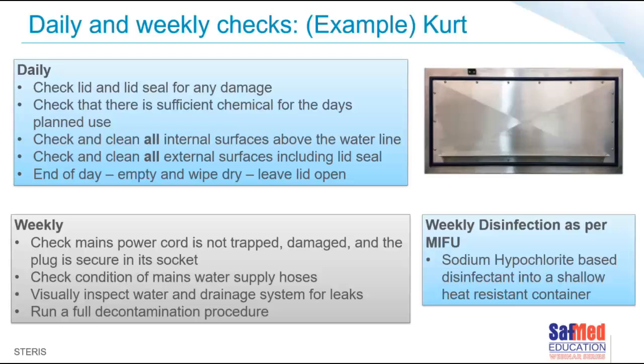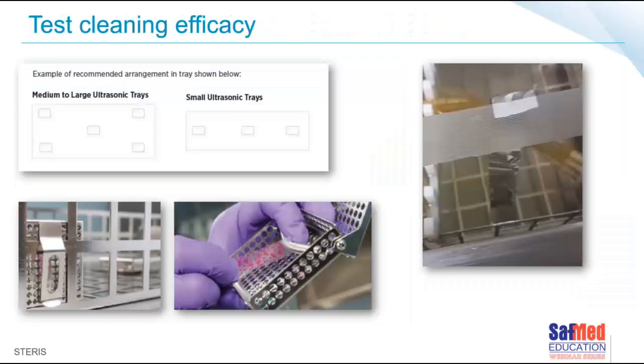Thanks. Like all pieces of cleaning equipment, like our automated washer disinfectors, we want to make sure that the machine works effectively, and servicing is important. But we can, of course, use test devices to check that the machine is working effectively. We've spoken about it in the past, and it's in the CFSA's SOPs as well. We've spoken about using the foil test, which is indeed one method of testing the efficacy of the machine.